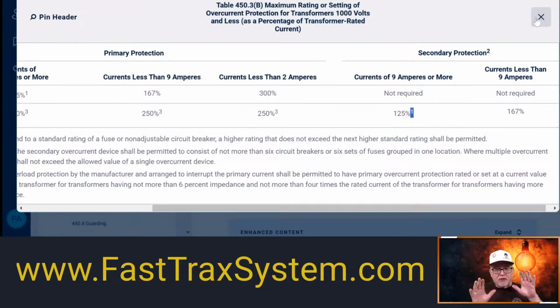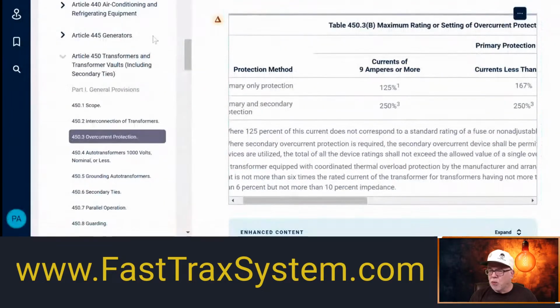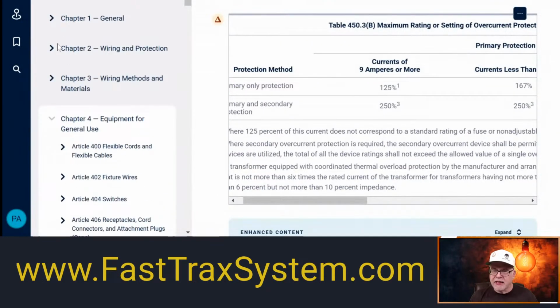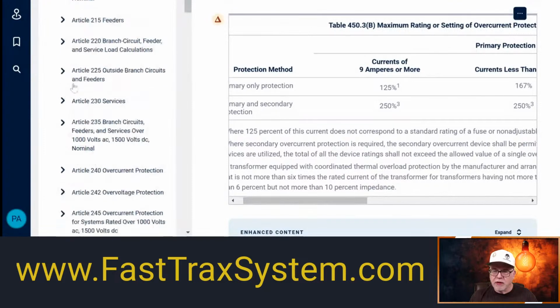Now this is a standard situation where you have a transformer feeding a panel in your commercial environment. Everyday situation, okay? So I've got to have that protection, so those conductors terminate into the overcurrent device that's in that panel, okay? I'm trying to give you an everyday example. So now I need to see what is the overcurrent device that I can use here. I'm doing this to illustrate a point.